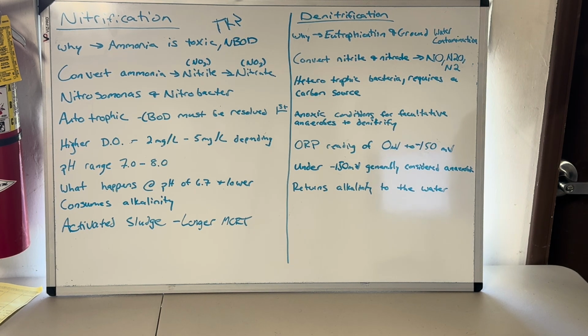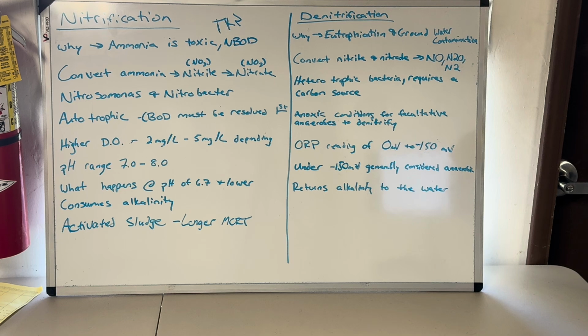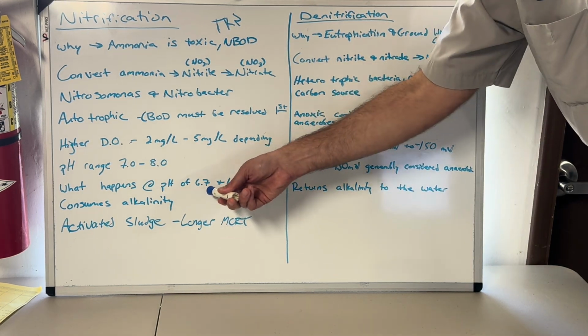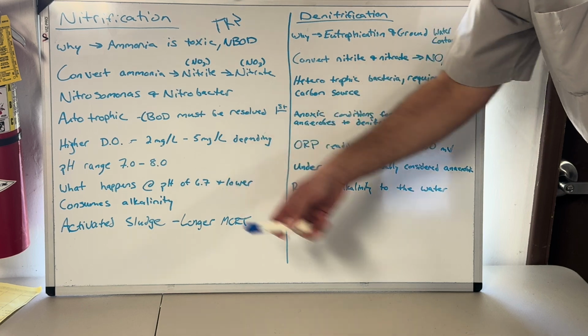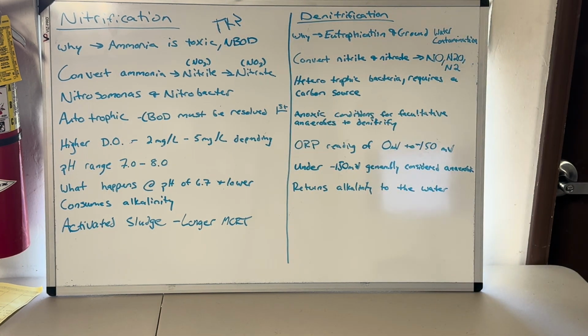And now I'm giving the plant medicine when we should have never gotten here, so I'm just talking from experience there. Pay attention to your alkalinity, because if you're getting to a 6.7, you may be ready to fall off a cliff and start plummeting to those lower pH levels. So yeah, at 6.7, they start struggling with oxygen uptake.